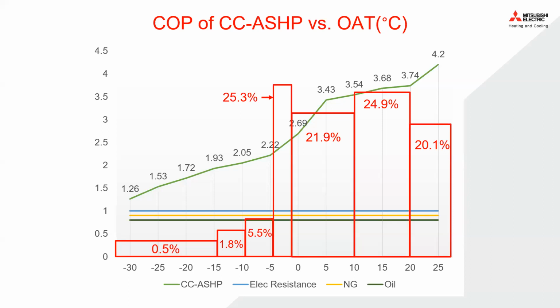Now, what I've done here is overlaid this with these bars, and what the bars indicate is the time spent at these various temperatures. We'll see in some following slides the temperature averages over 4 years for the various cities. This one happens to be Toronto. As you can see, we spend 25.3% between -5 and -3, 21.9% from -3 to +10, 24.9% from 10 to 20, and down below -15, only 0.5%. So we're actually spending over 90% of our operating time above a COP of 2.